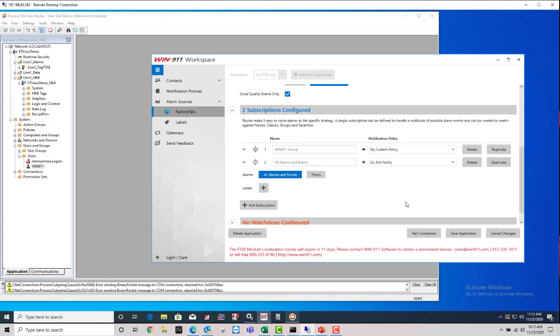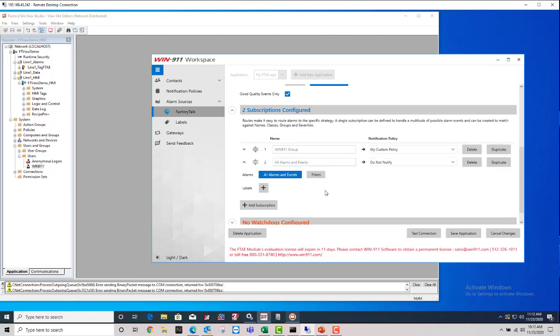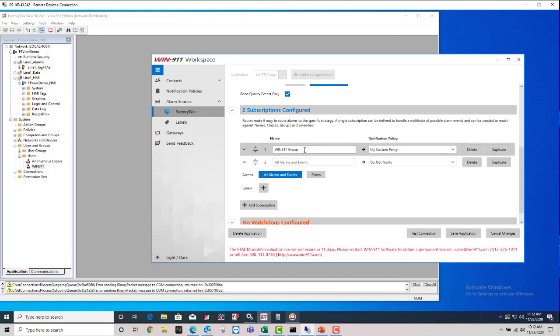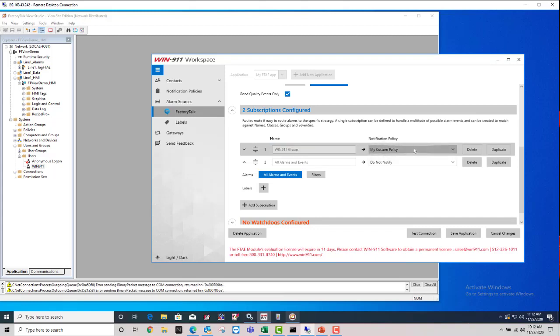And the alarms can only match one of these subscriptions, right? So if you create a list of five different filter criteria for your subscriptions, an alarm can only match one. As soon as it matches one, let's say it matches the Win911 Group, it goes to that notification policy and it's done. It's not going to match against multiple. So these are just kind of like firewall rules. Once it matches one, it goes there and it's done.